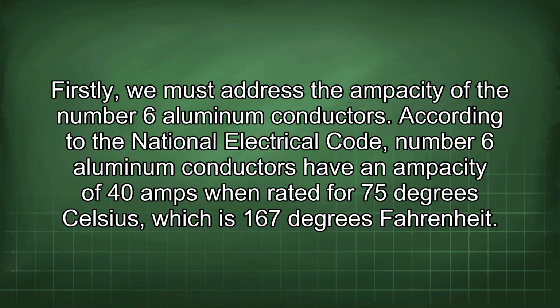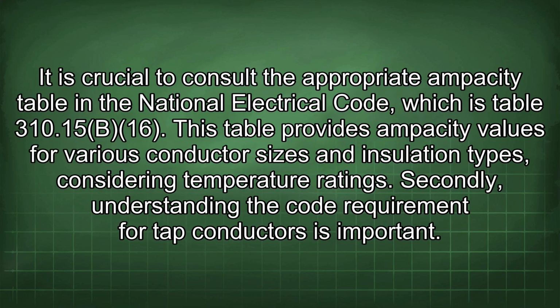According to the National Electrical Code, number 6 aluminum conductors have an ampacity of 40 amps when rated for 75 degrees Celsius, which is 167 degrees Fahrenheit. It is crucial to consult the appropriate ampacity table in the National Electrical Code, which is Table 310.15(B)(16). This table provides ampacity values for various conductor sizes and insulation types, considering temperature ratings.